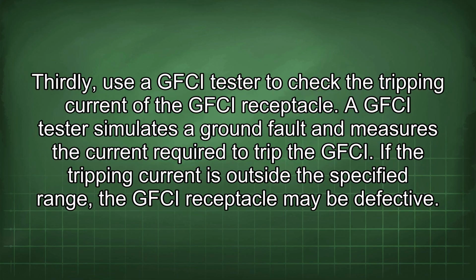Thirdly, use a GFCI tester to check the tripping current of the GFCI receptacle. A GFCI tester simulates a ground fault and measures the current required to trip the GFCI. If the tripping current is outside the specified range, the GFCI receptacle may be defective.